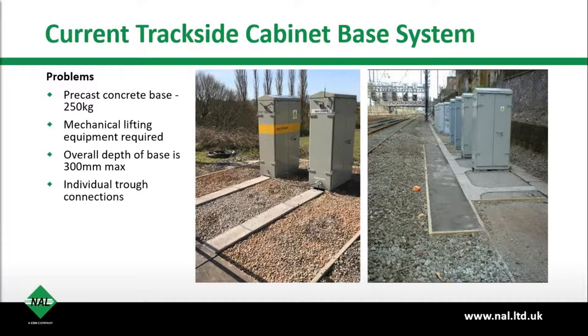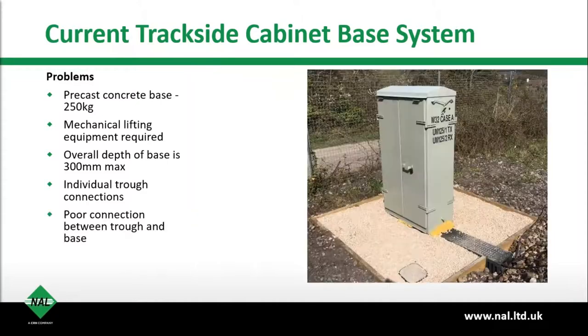And then when it comes to interacting between the cabinets, all of these troughs are going to be full with loops of the same cable. They're going to be chock-a-block with a very hard to unpick jigsaw puzzle or spaghetti junction of cables. And it makes it terribly difficult when you're maintaining or removing life expired cables or having to replace cables. It just makes life more difficult than it needs to be.